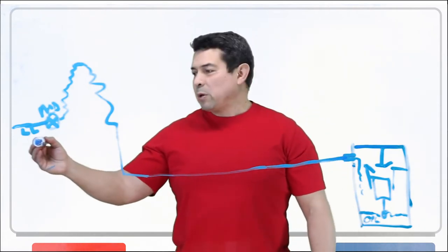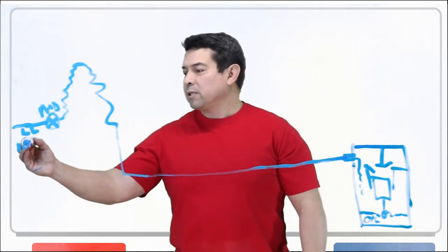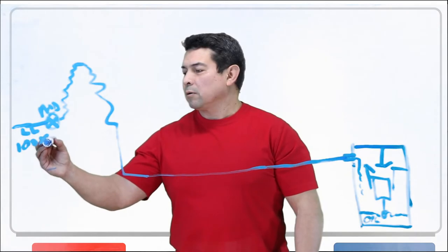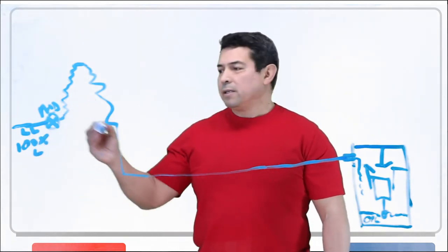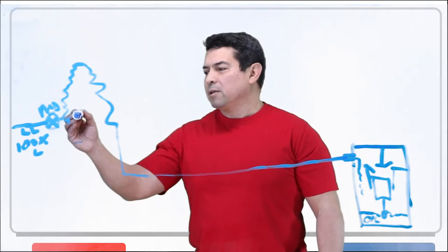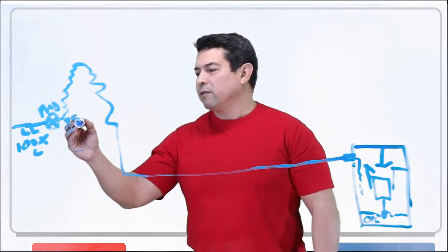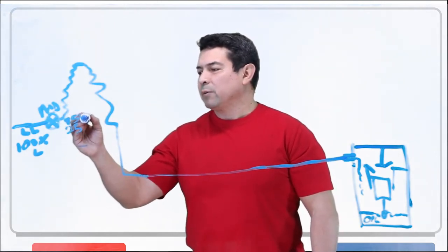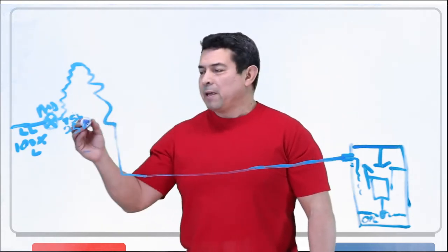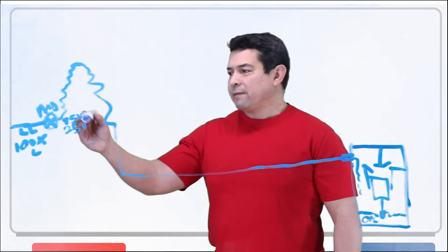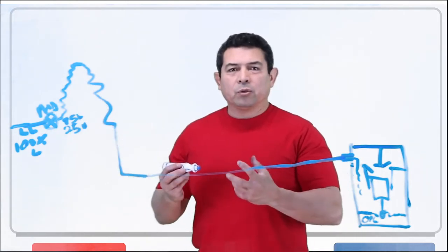Now coming into the metering device, we're supposed to have 100% liquid. Coming out of the metering device is going to be approximately 75% liquid, 25% vapor coming out of the metering device. As it goes into the evaporator, that 75-25 is going to change.